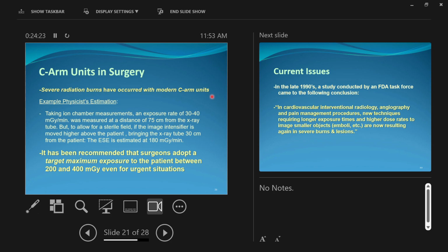And let's see some numbers here. So this is a physicist's estimation. An ion chamber, which is a radiation detection instrument, measured an exposure rate of 30 to 40 milligray per minute. So you can take that and multiply it by 5 minutes and see what it would be after 5 minutes. But 30 to 40 milligray per minute at a distance of 75 centimeters from the X-ray tube.